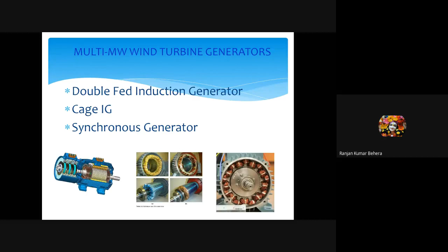One is DFIG. Most importantly today, the government requires that your wind power or wind generator must be connected to the grid. If you don't connect, and suddenly there is some abnormality causing you to disconnect from the grid, the complete system will start oscillating. That's why the most important performance requirement today is low voltage ride through performance.